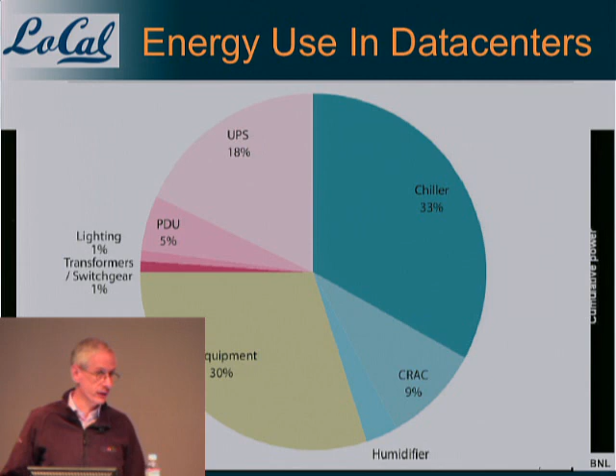So there's a pretty heavy overhead associated with feeding and cooling the equipment, not just the equipment itself. This is a pie chart that shows some of the sources of where that energy footprint goes: the chillers to cool the machine rooms, the air movers, the so-called CRACs, computer room air conditioners. The IT equipment in this particular case is less than one-third of the overall energy pie that goes into a typical data center.